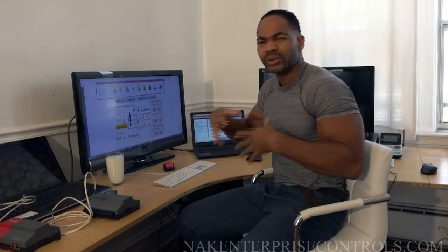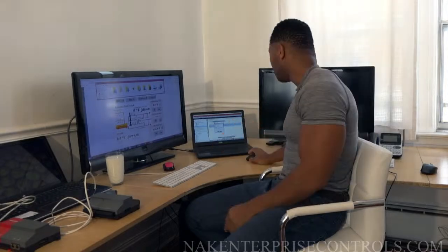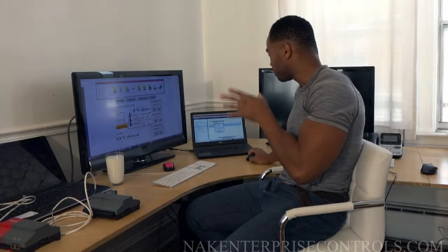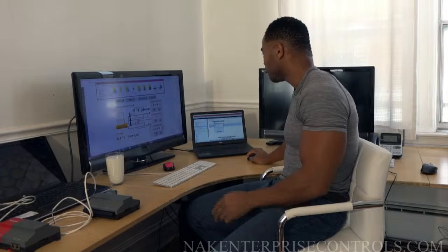You don't get any temperature sensors. You don't get anything at all. You're not getting any data. That could be a certificate issue. So just head into your server and make sure the certificate for that particular station is approved. We'll do that and you'll see the difference.